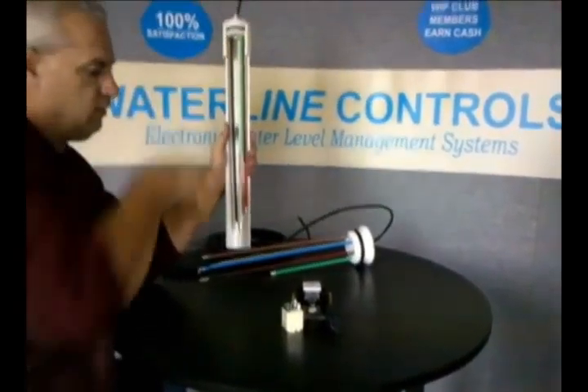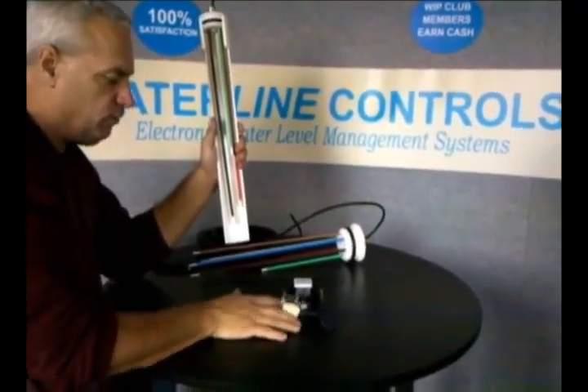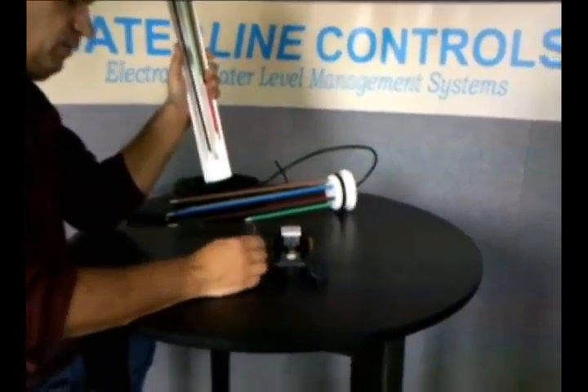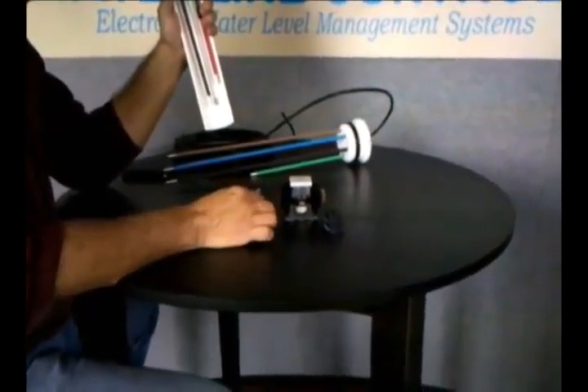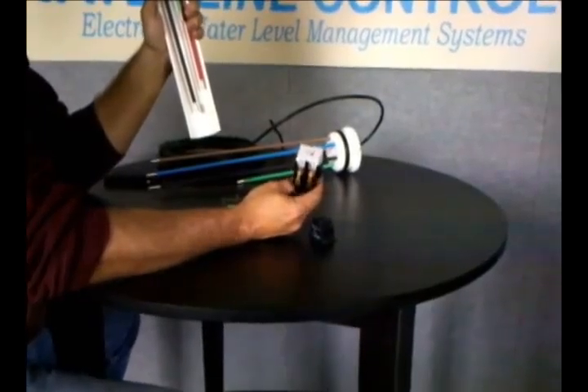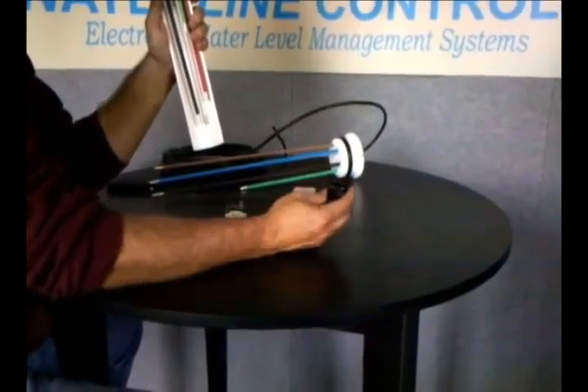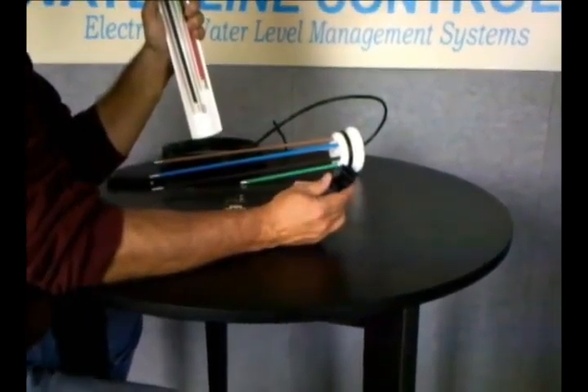This thing senses through this circuitry and then fires these water level switches, which are also called relays. This relay could be used to fire a well pump—it's rated for 5 horsepower. This one is basically what we classify as a pilot relay.